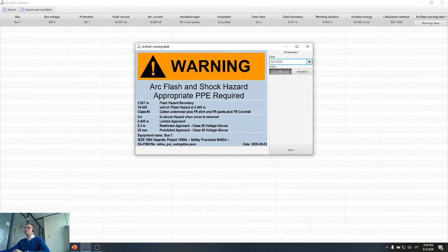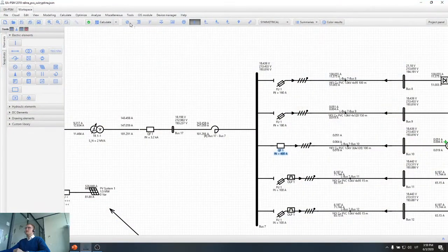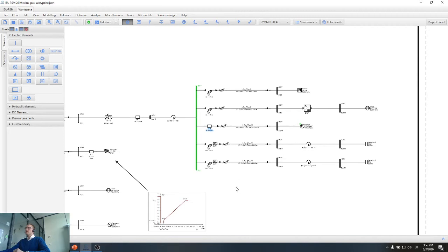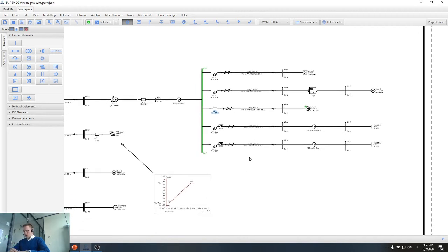And class 3 personal protection equipment only requires cotton underwear plus a fire resistant shirt and fire resistant pants, plus a fire resistant coverall. So now we don't need the flash suit, which is good. We only need the fire resistant coverall, and this will be enough to protect the person from severe damage in case of a worst case scenario, or in case of short circuit in the electrical network. So we can see that with software it is possible to calculate technical things in order to protect not only the equipment, but also the persons who are working with the network.